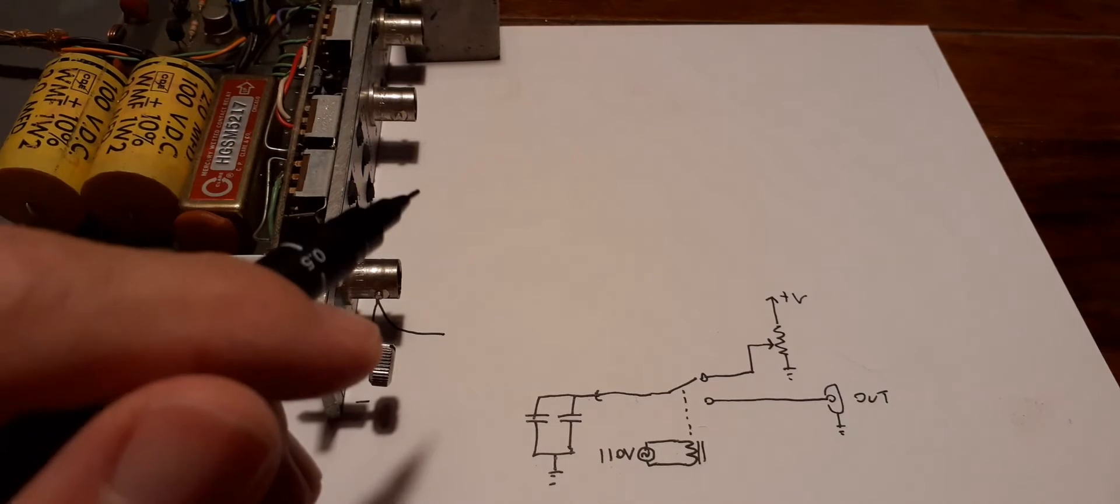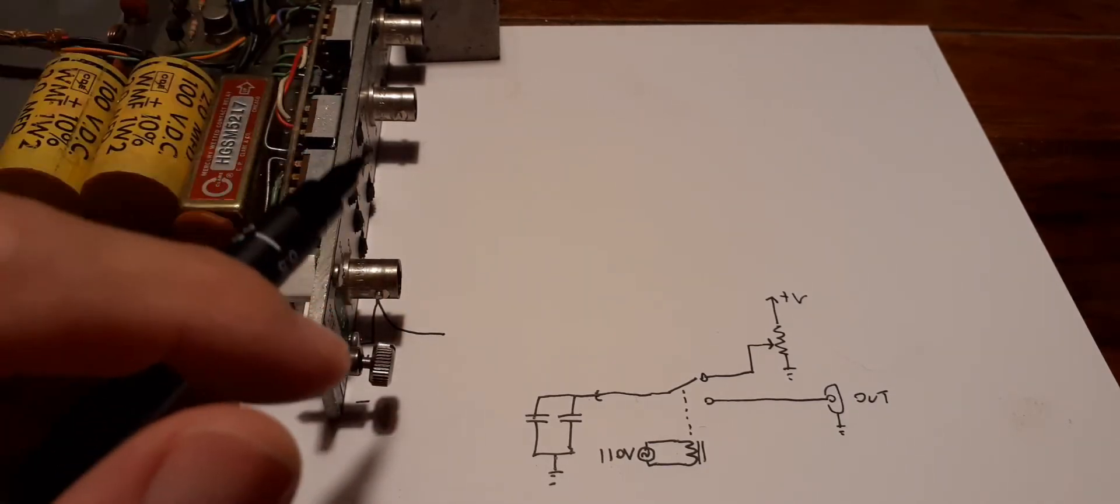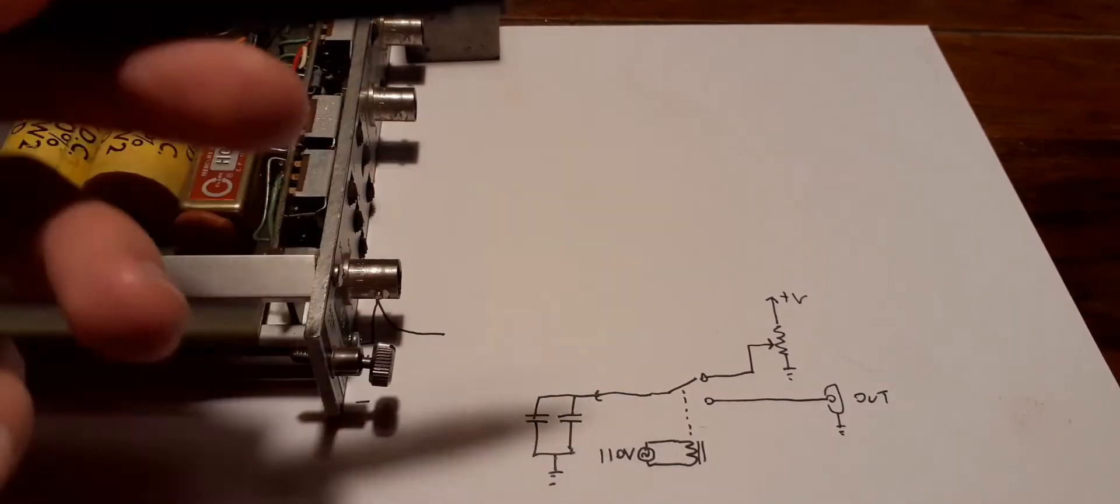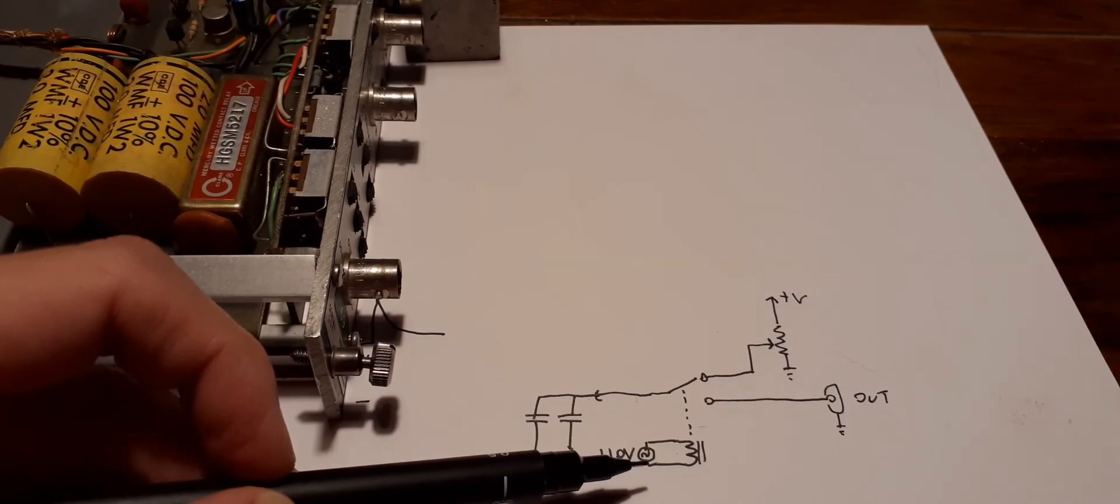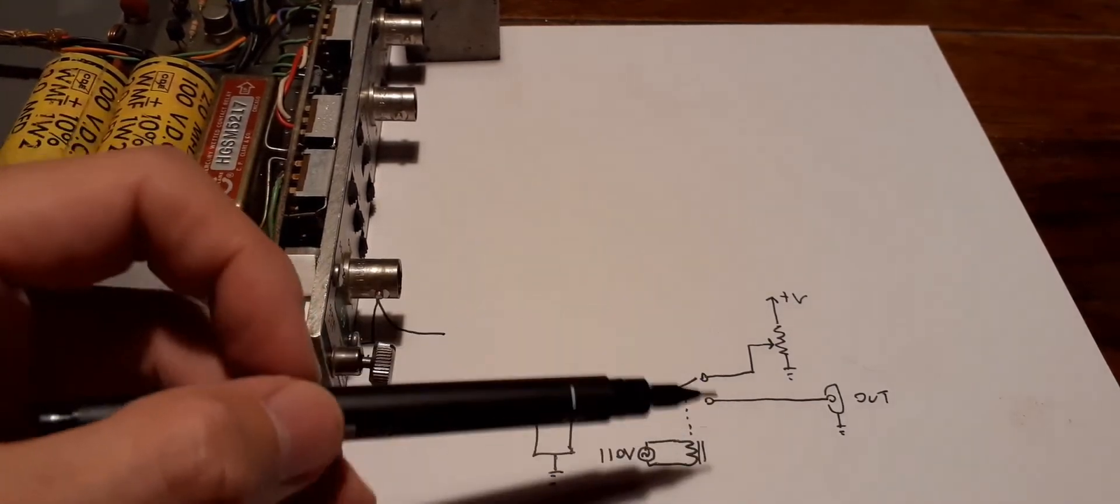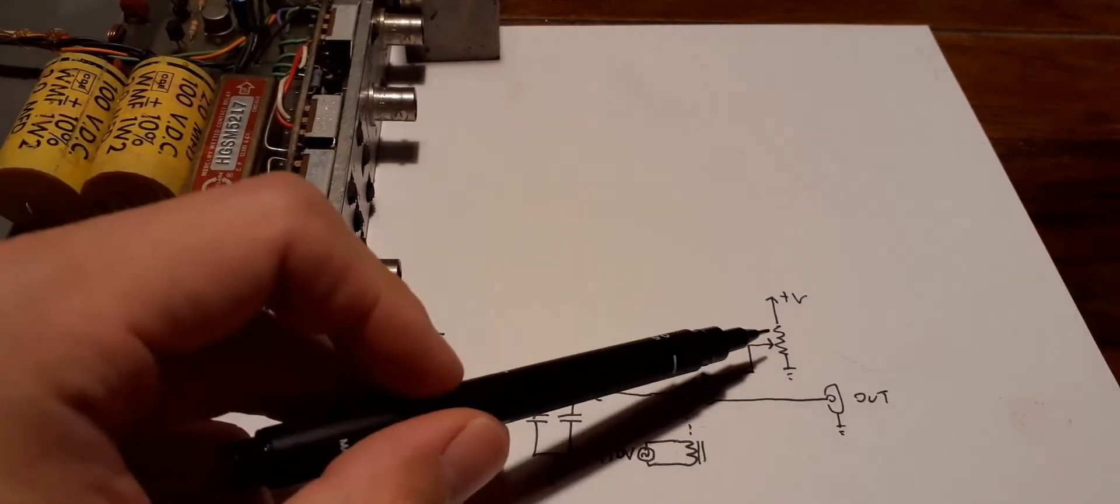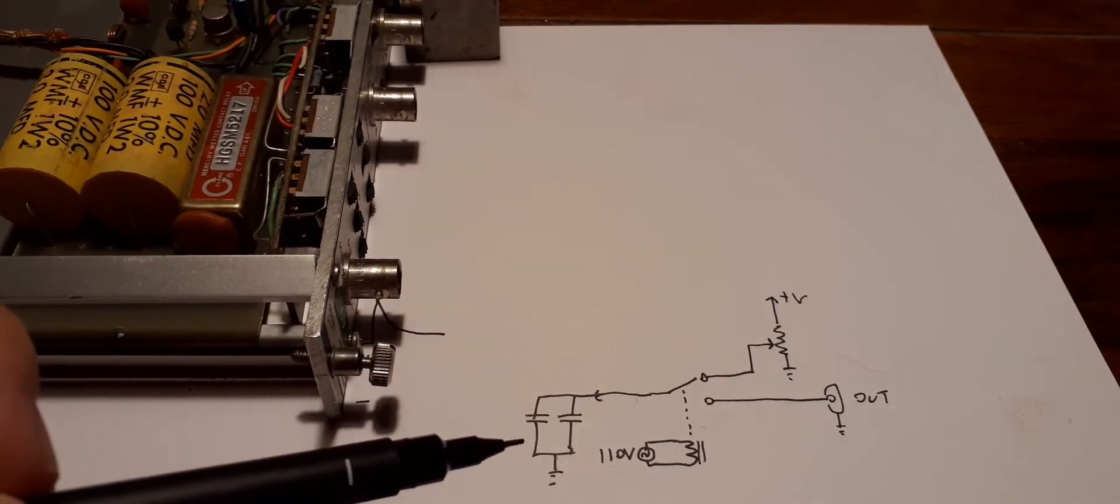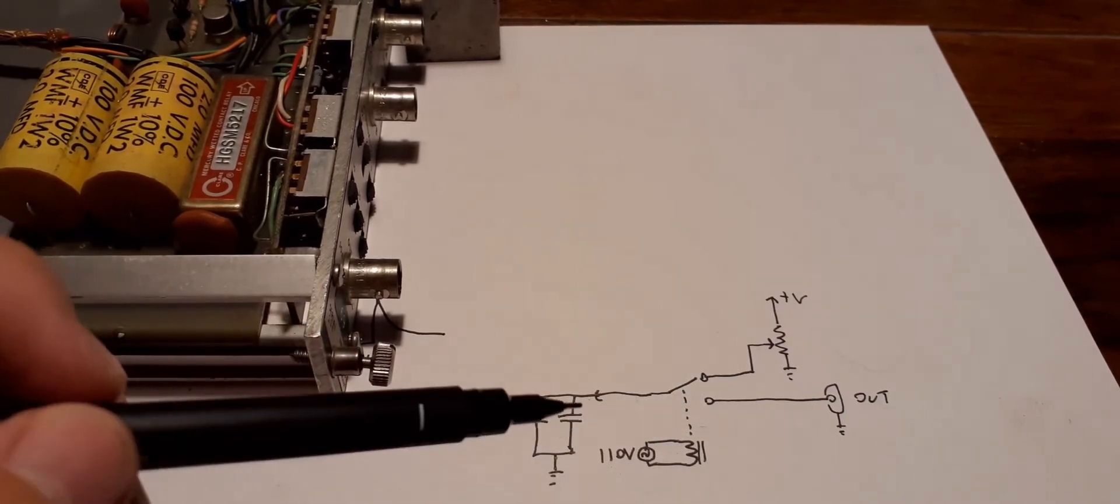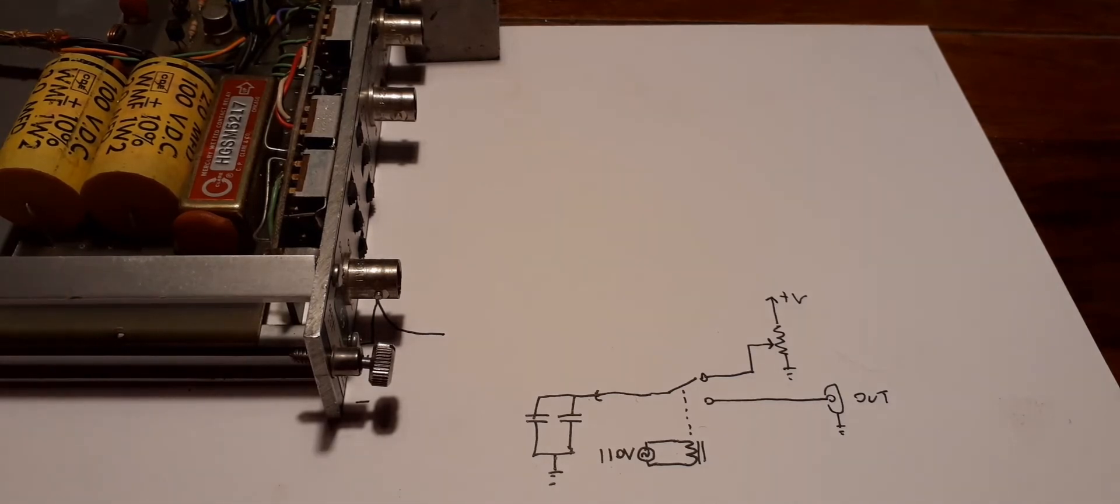There's literally no more to this than this, except that there's a few transistor buffers around, and then of course the front panel logic and switches. Basically, the mercury relay is just continuously flicked on and off by the AC voltage—it's unfiltered AC from the NIM bin. Thus it just changes between charging and discharging these capacitors, and the voltage they charge to is set by this potentiometer. The reason this works is because this mercury wetted relay is able to switch so quickly and so cleanly. I think if you replaced it with a normal relay you would see something very terrible.